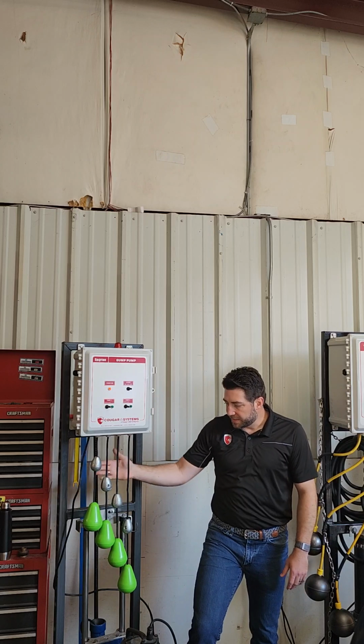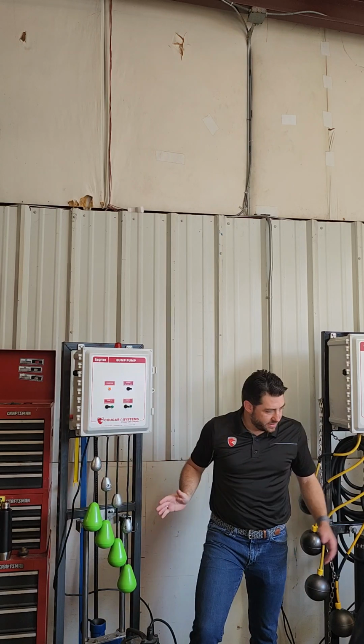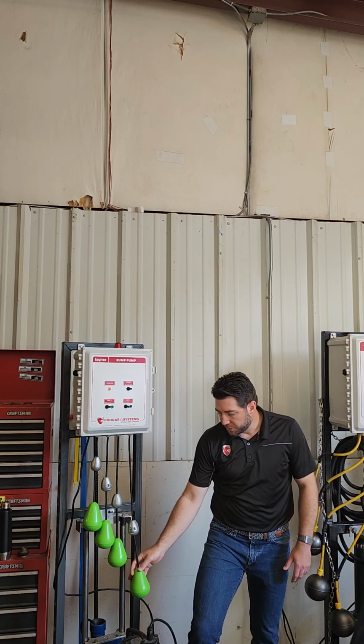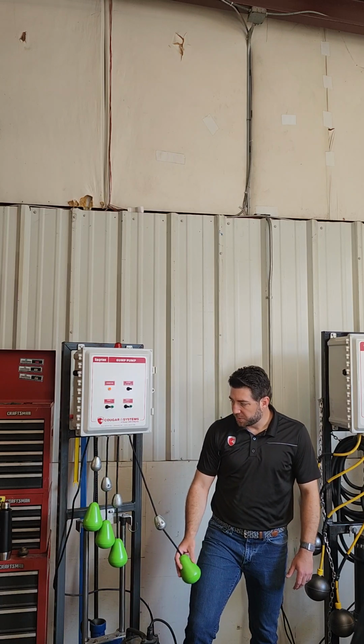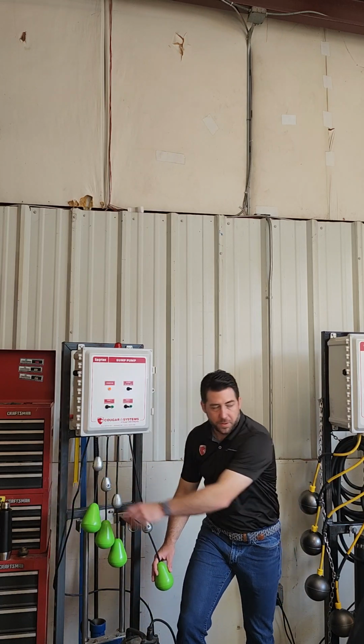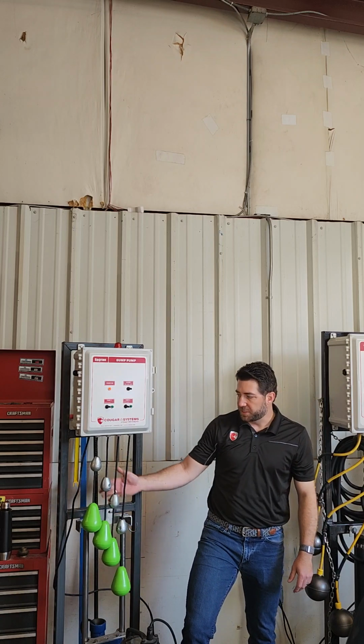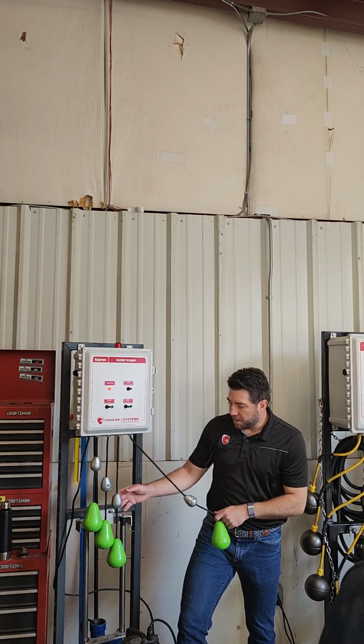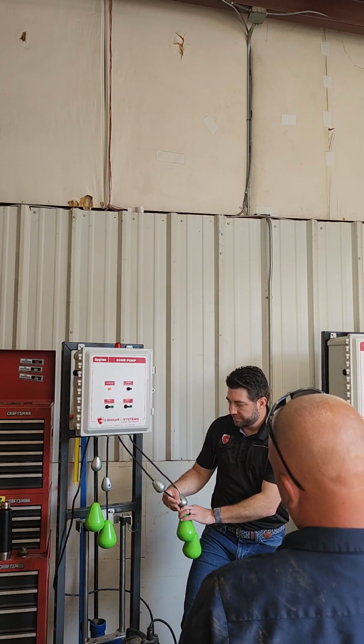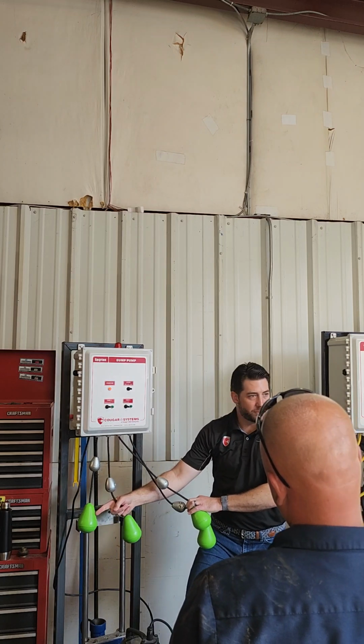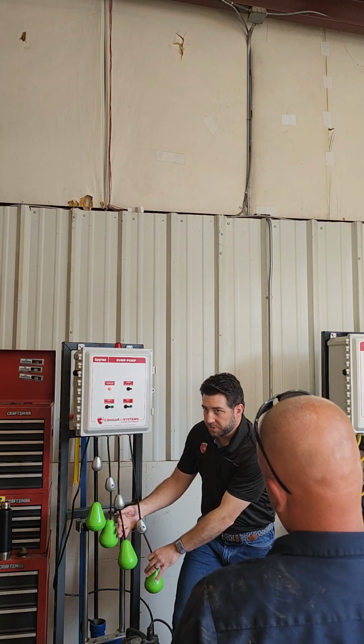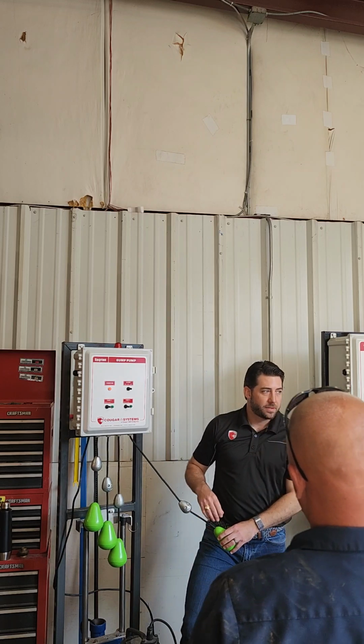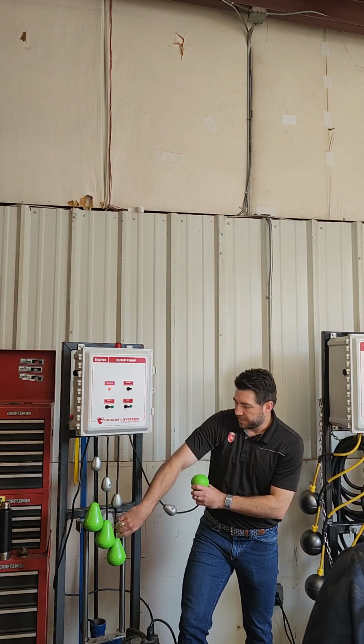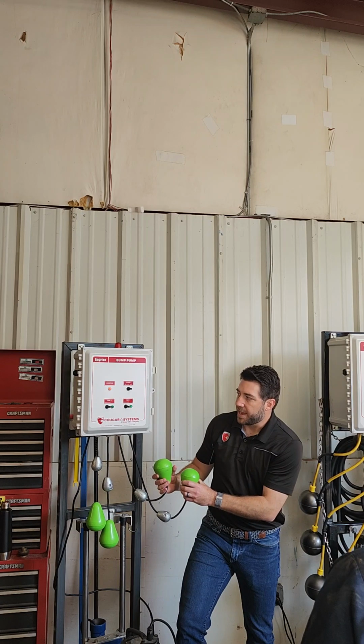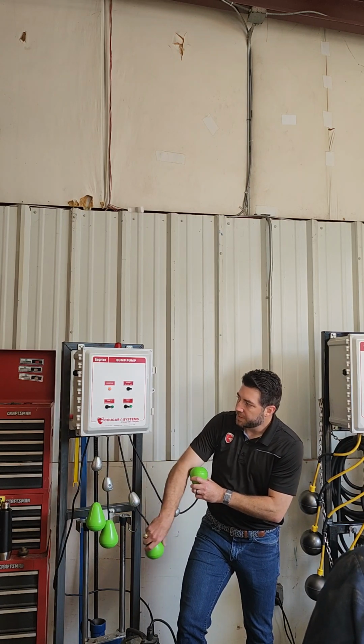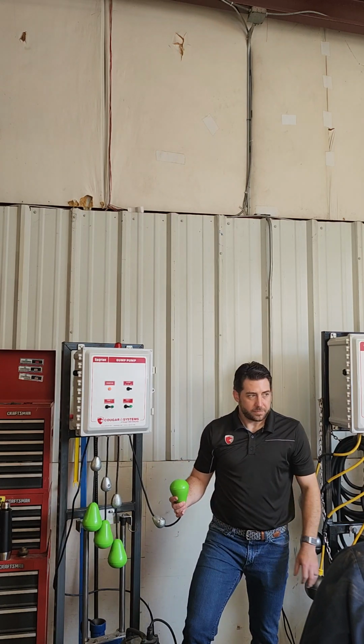One of the big things with any of these types of panels on the floats is that the first float switch and the last float switch are important in this sequence. If we're talking about 4 float switches, this is your all pumps off, lead pump on, lag pump on, and high level alarm. But the whole sequence has to start with this one. When this one comes up, it allows everything else to happen. Now you can see that pump's turned on, but it's going to stay on until this goes down.